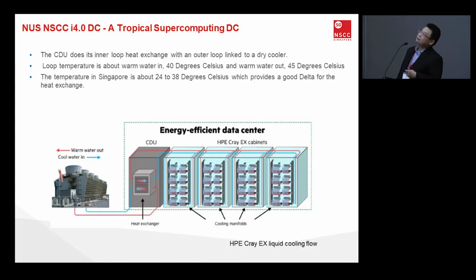So now we talk a bit about the Cray system. There are two internal loops running. One is within the Cray itself, the liquid cooling. The temperature within the liquid cooling is about 40 to 45 degrees. The input into the system is about 40 degrees, and the output from the system is about 45 degrees.